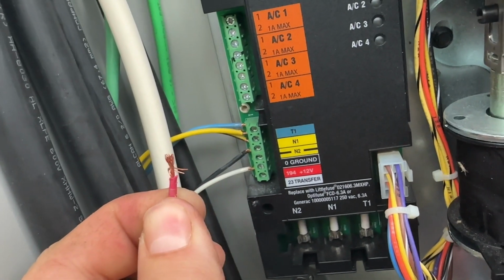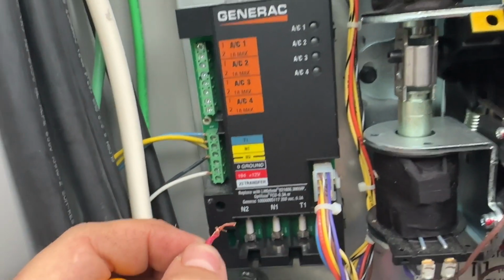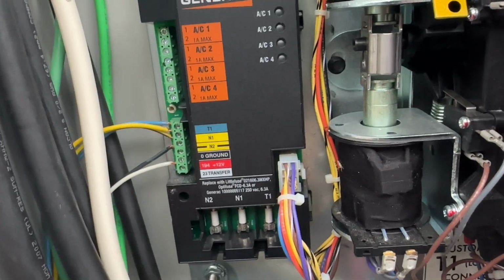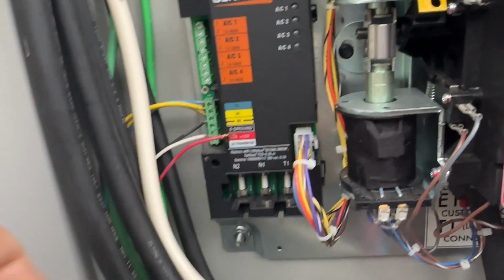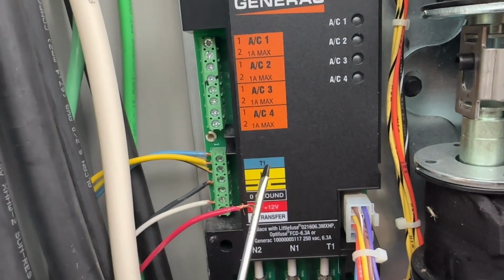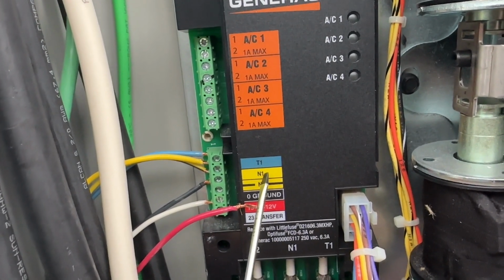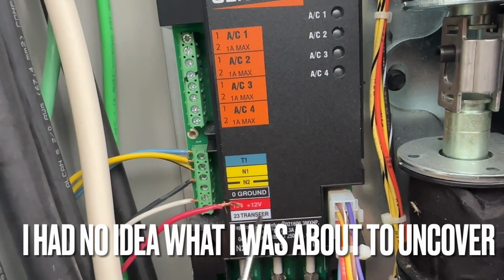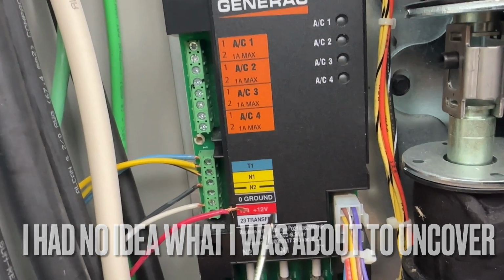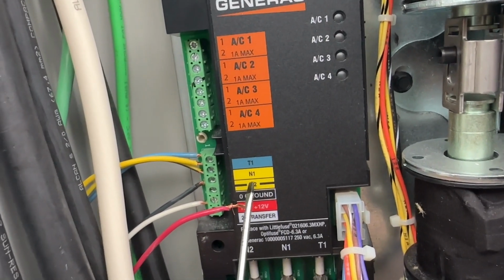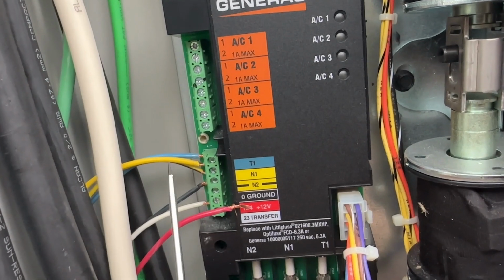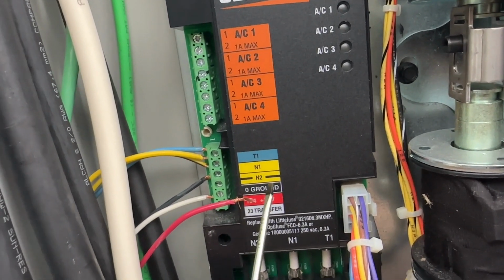So that was my issue. That's going to be your issue if you got 2099. You have a voltage, again, I'll clarify for this video. This video helped you, thumbs up. You have a voltage leak between T1, between N1 and N2, or between these 23 and 194. So that just means that these wires would be crossed, so it's sending power down a signal wire that shouldn't be occurring. So this would be your issue.